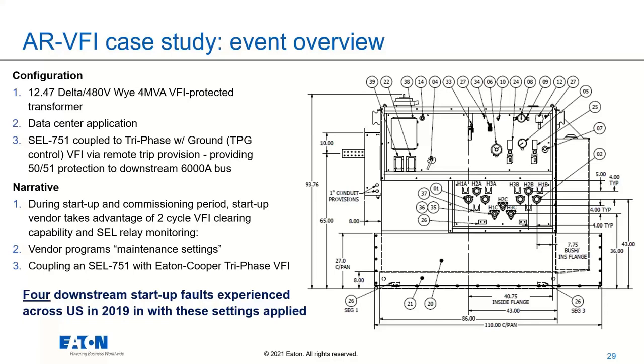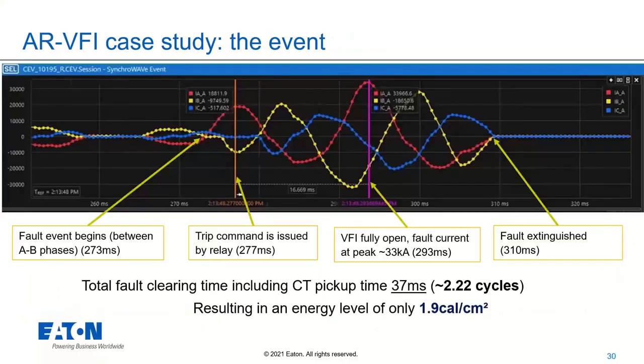There might be, as we're going to see in these next images, things like shipping supports that are still in the way that could cause a fault. So it's very important not to use things like inrush blocking, where I'm just not looking at any fault conditions during the startup. I'm going to ride through inrush and then I'll activate my protection settings. Well, if we do that, you might ride right through what is an actual fault. So this always on fashion is a much more concise and clean way to do this protection.